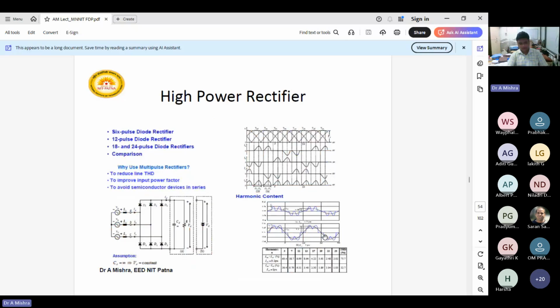So for high power rectifiers, this is a 6 pulse rectifier. Why did I say 6 pulse? Then 12 pulse, 18 and 24 pulse. Multi-pulse, what is the purpose? I told you 1 pulse, 2 pulse, 4, 6 pulse. If you are increasing the pulse number, definitely your complexity is going to increase. But why are we going for it? We are going because it is reducing the harmonics.